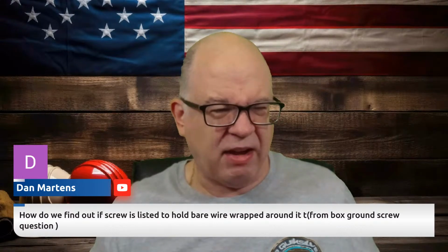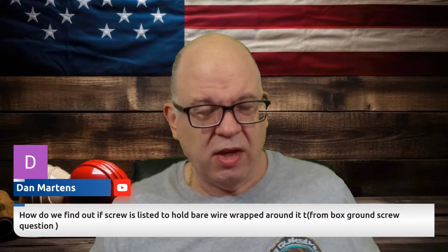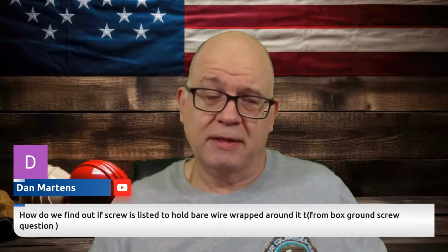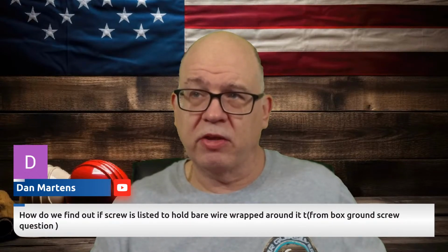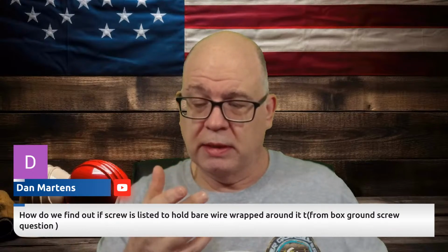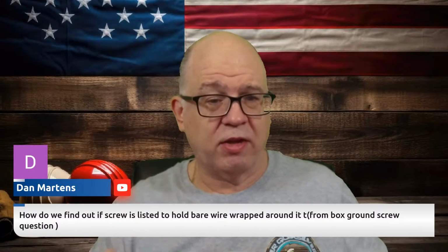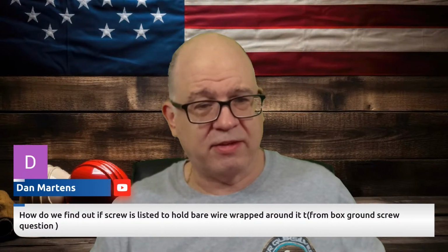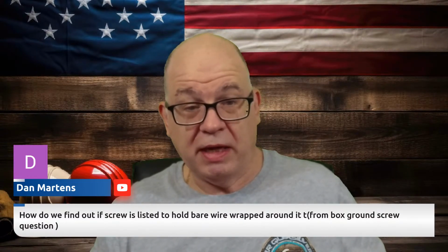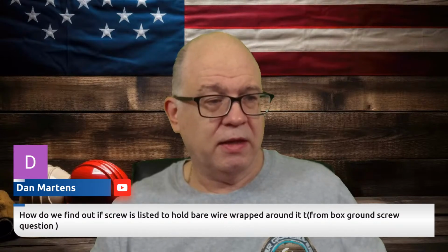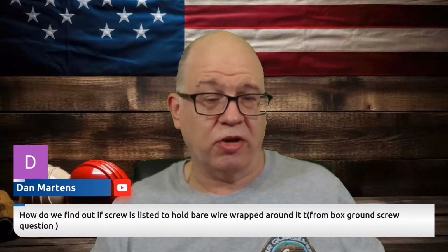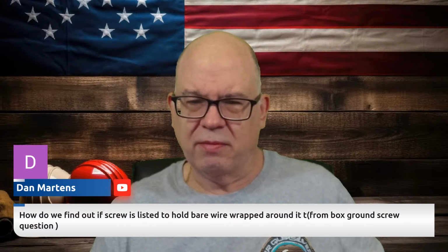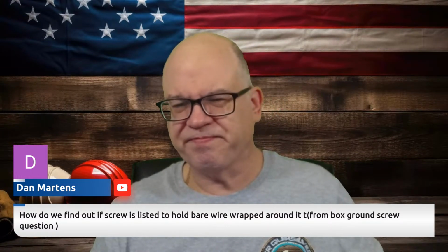Dan says, how do we find out if a screw is listed to hold bare wire wrapped around it? Well, most of those screws for boxes, Dan, are going to be green in the box for that application. And usually you're going to have something on the actual box that they come in that'll tell you that it is either listed or identified for grounding purposes, maybe under UL 486 or something like that. So that's typically what you're going to see. When you go looking at the bonding in the box, typically the green screws with green finish, you already know those are going to be okay for the box. So that's typically how you would tell.